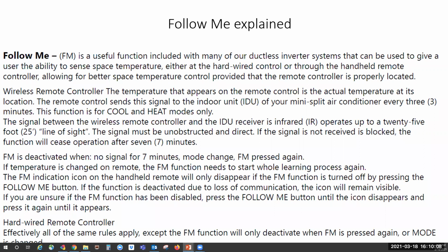Basically what it is, the follow me mode senses the temperature at the controller. So whether it is a remote control or a wired controller, it would sense it at that place. If it is a remote control, it has to have line of sight. It has to be within 25 feet in order for it to get the proper reading from the remote control. Now, if somebody walks by and throws a coat over it or something, after 7 minutes it checks, there's no signal, and it goes back from the remote control sensing to the return air sensor and senses it up there at the unit. And then once again, all you have to do is push the follow me button and it will take back over from the remote or the wired controller.